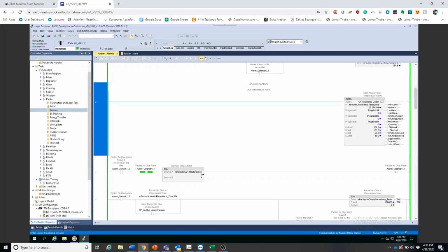If you notice, if the alarm level is active and none of the alarm conditions such as high high, high, low, low low, or low alarm will be highlighted in green to the right. And as you can see, nothing is highlighted green. So now, if you go and you click in the value and you write 181, you notice that the alarm went up. Notice how the high alarm condition came true.